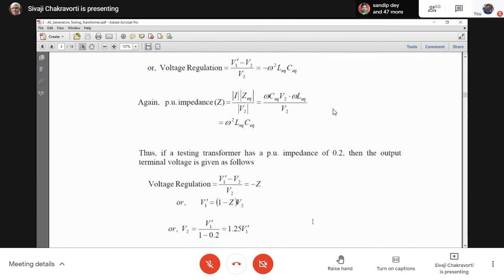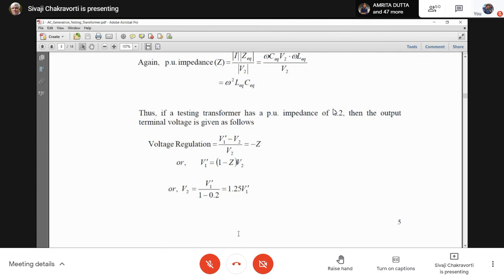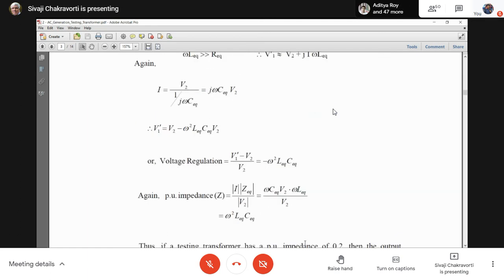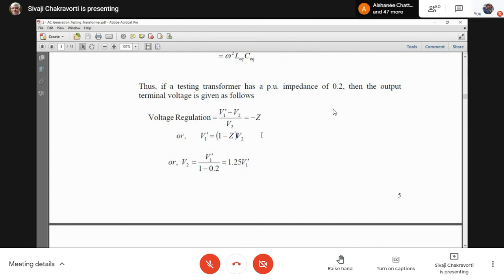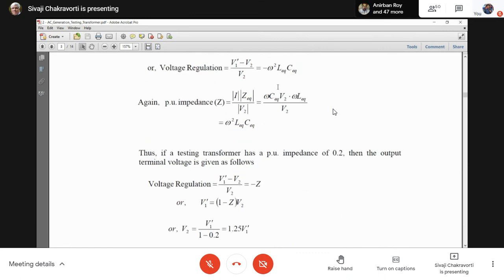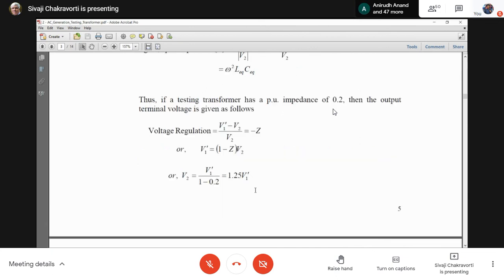So if a testing transformer has a per unit impedance of, say, 0.2, what will be the relationship between V2 and V1 prime, where V2 is the terminal voltage and V1 prime is the transformer end voltage? We can put it in this expression here. Voltage regulation is (V1 prime minus V2) by V2, and this is equal to minus Z. That is from these two expressions, voltage regulation and per unit impedance. So V1 prime is nothing but (1 minus Z) into V2. So V2 is V1 prime divided by 1 minus 0.2, or 1.25 V1 prime.